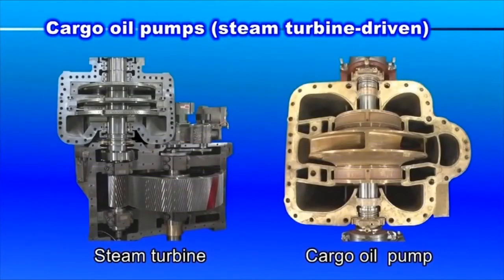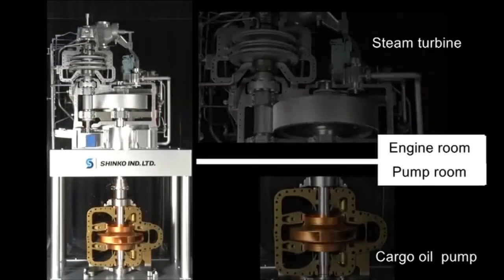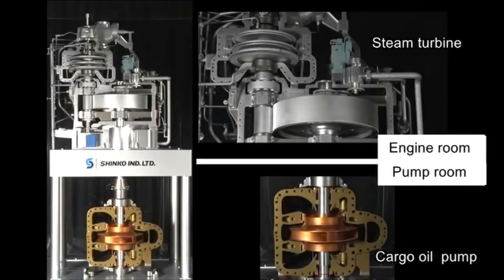Steam turbine driven cargo oil pumps are used on crude oil tankers. With its steam turbine side placed in the engine room, the cargo oil pump proper is installed in the pump room via seals for the gear coupling and penetrating parts. This isolation is necessary from the viewpoint of hazardous material handling.